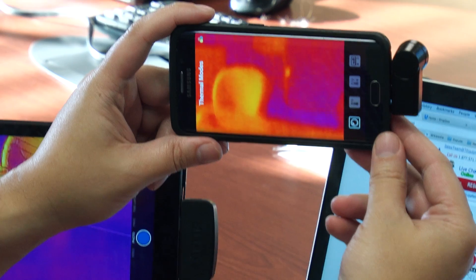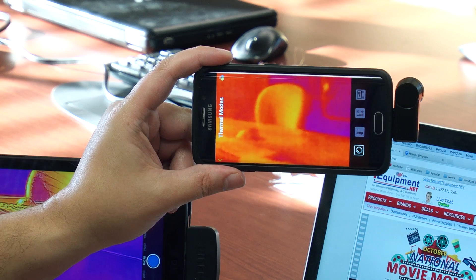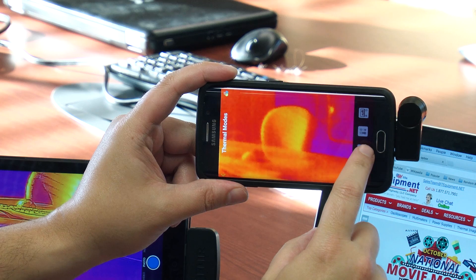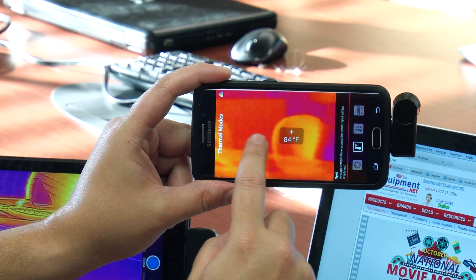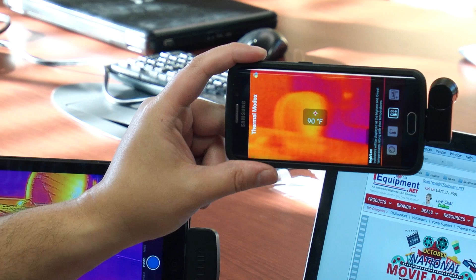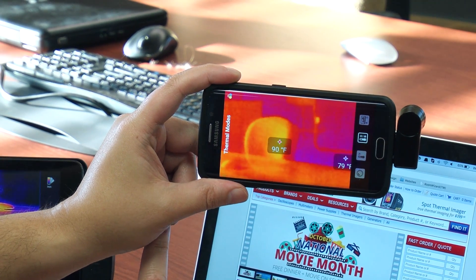So here we're going to look at first the Seek. This is the standard Seek camera that I have on my Android-based phone. It gives you pretty good resolution and pretty good clarity on the thermal image. If you want to see some information about what you're looking at, you can go in and get a center spot measurement. Unfortunately, you can't move the spot around, but what you can do is go into the high-low mode, which will automatically show you whatever the coolest and hottest spots are in the field of view. It's very convenient for finding a difference or a delta between the two temperatures.